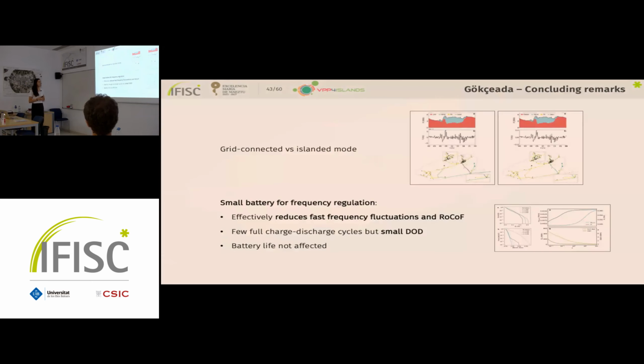To conclude this part, we have analyzed two different grid operation modes, and we have seen that they have large differences, especially in the size of frequency fluctuations. We have seen that using a small battery can be helpful for frequency regulation, because it reduces very effectively the fluctuations of both the frequency and the ROCOF, and that using the battery for frequency regulation does not reduce much the battery life.